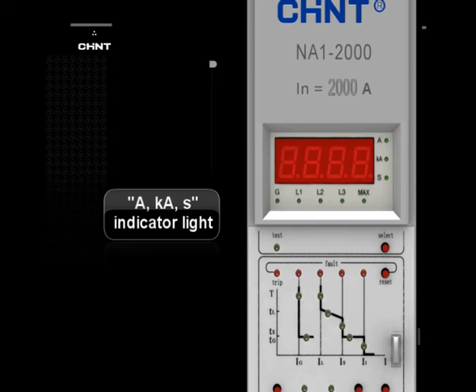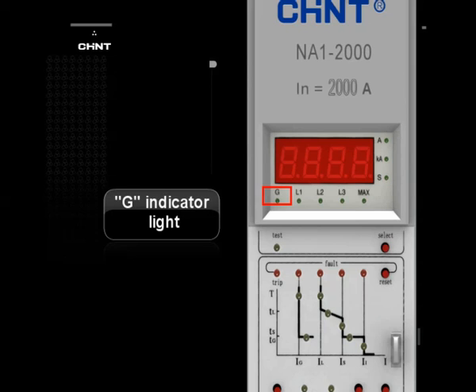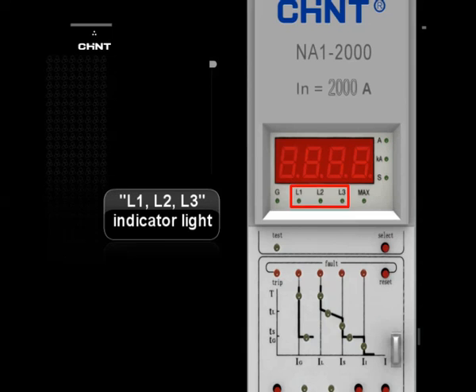"A, kA, s" Indicator Light: Indicates the unit of the displayed value. G Indicator Light: Indicates the displayed current is earthing fault current. L1, L2, L3 Indicator Light: Indicates the phase of the displayed current. If the MAX indicator shines simultaneously with one of L1, L2, or L3, it shows that the displayed phase current is the maximum among these phases.